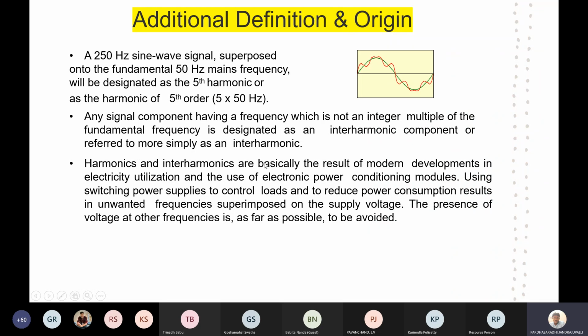Harmonics and interharmonics are basically the result of modern developments in electricity utilization and the use of electronic power conditioning modules. Using switching power supplies to control loads and to reduce power consumption results in unwanted frequencies superimposed on the supply voltage. The presence of voltage at other frequencies is to be avoided as far as possible. By observing the diagram, this is the 250 Hz component, whereas this is the 50 Hz component.